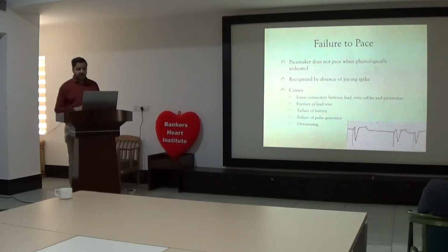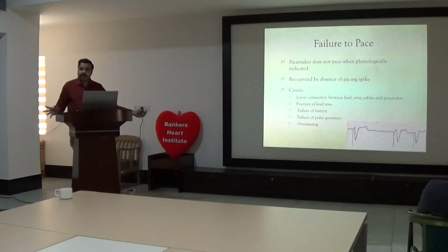The third problem with a pacemaker is failure to pace. Everything is okay, still the pacemaker does not pace. Like in this case, QRS is being paced, QRS is being paced, QRS is being paced, but between these two beats there is no pacing. Your rate is set at this interval, but there is no pacing spike over here. Why? Because the pacing spike is not delivered. There is failure to pace by the pacemaker. Nothing is wrong with the heart. Capture is being done, sensitivity is also okay, but this part is not being paced.